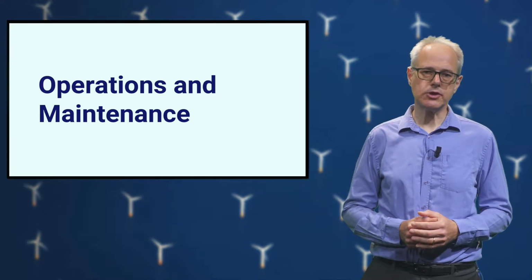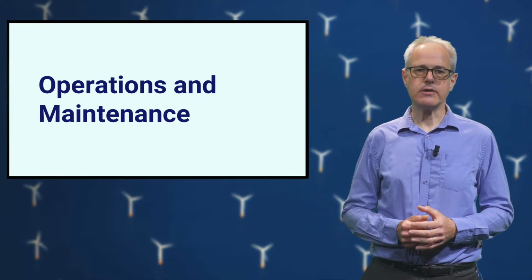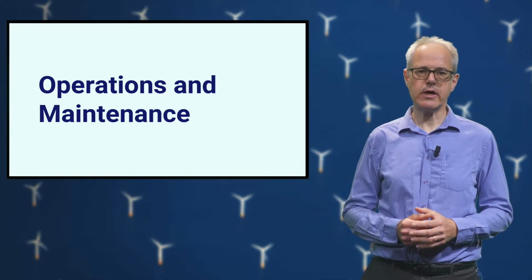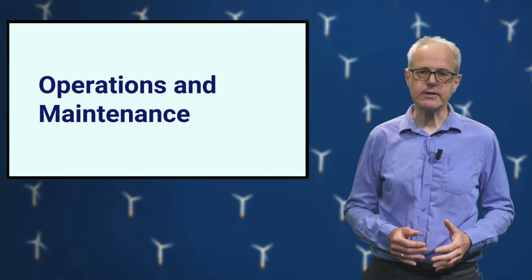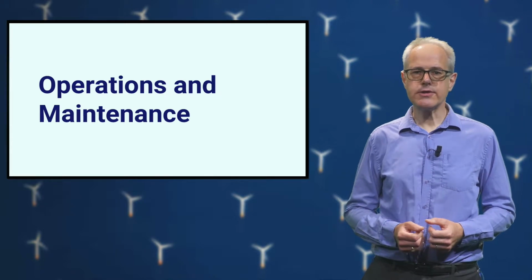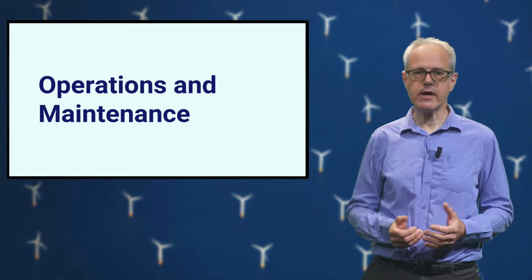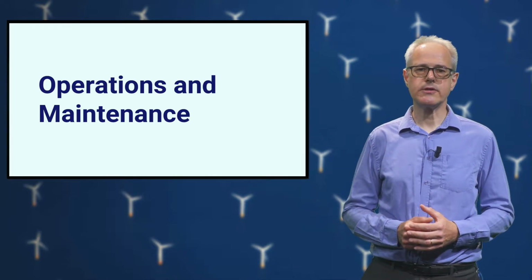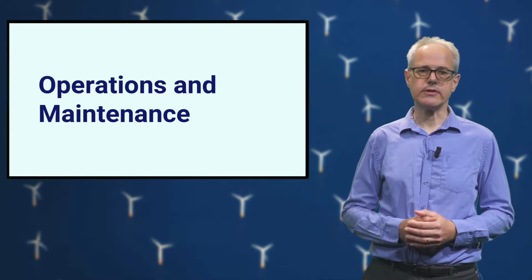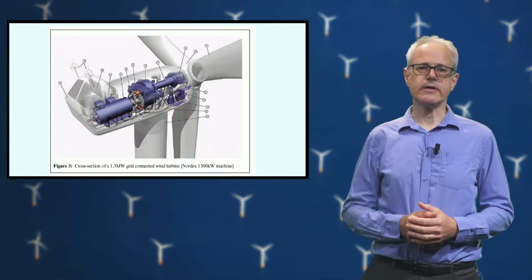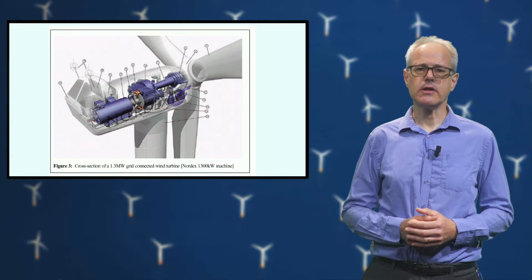The average wind speeds offshore are higher than onshore, and access is primarily by boat. Maintenance vessels can only operate in a limited range of wind and wave conditions. This means that particularly in winter, access can be very limited. The cost of chartering a vessel large enough to transport spare parts to an offshore wind farm is very high. This can cause the costs to mount up if the sailing of a vessel is delayed due to adverse weather conditions.